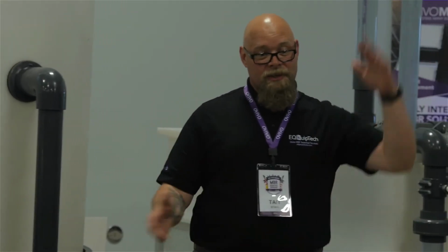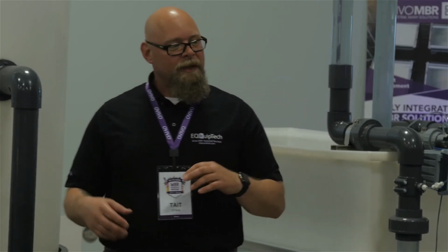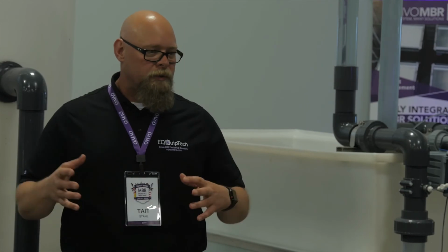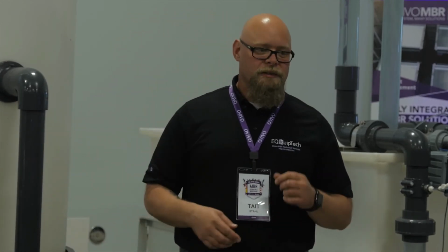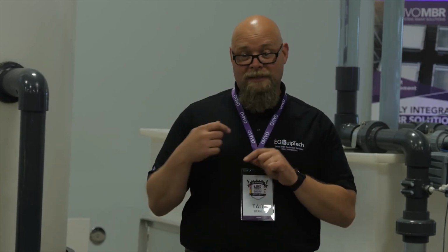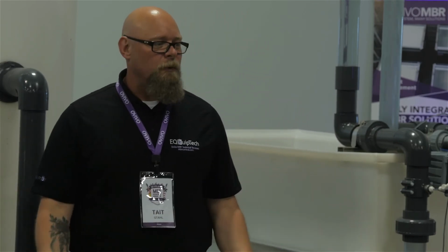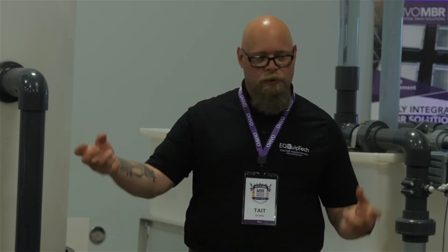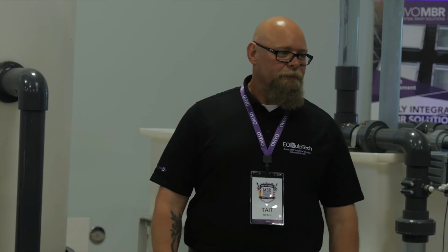But if you've got a suction lift system, especially if you're pulling several pounds of vacuum, there are leaks that can open up under vacuum that won't under pressure. Things that'll seal under pressure will open up under vacuum. And engineers want to jump through the phone and murder me when I say that because they're like, well, how do I check for that? And that's kind of one of the battles. But I think we're coming up with some pretty creative ways to check that out.